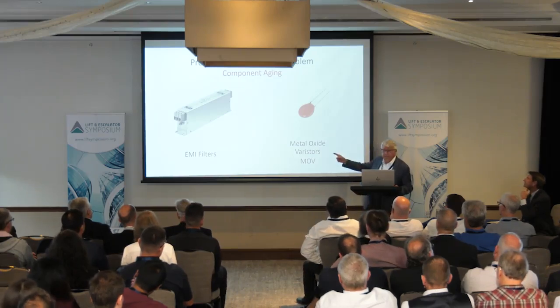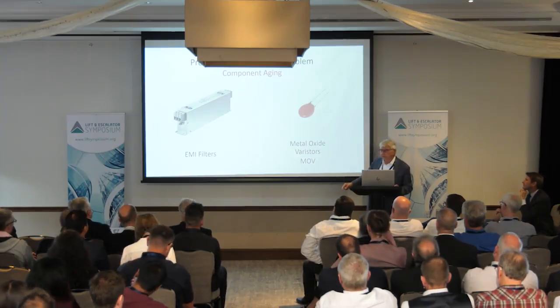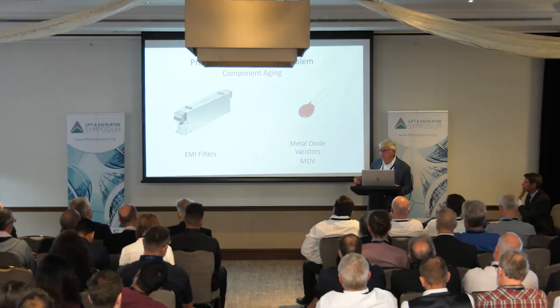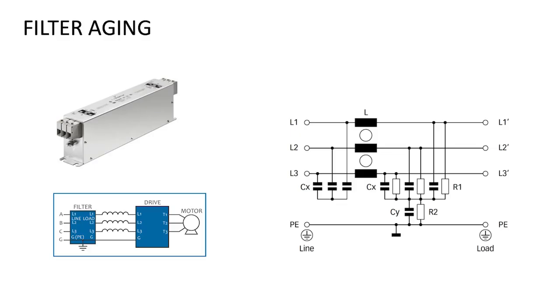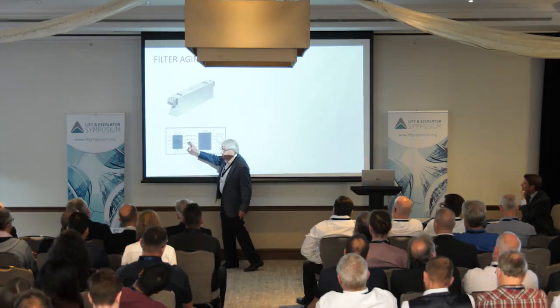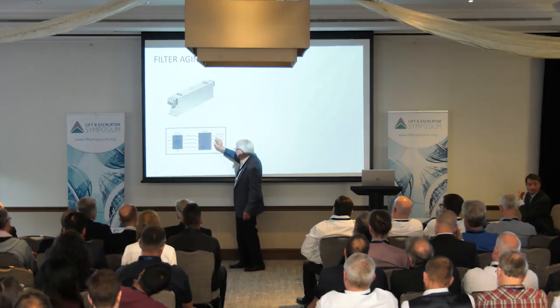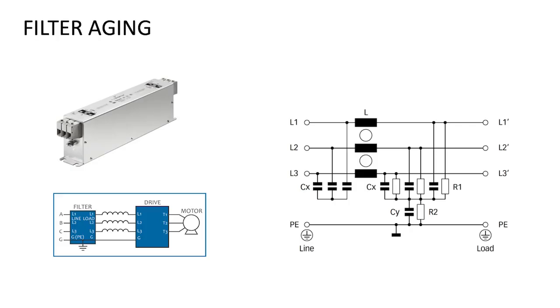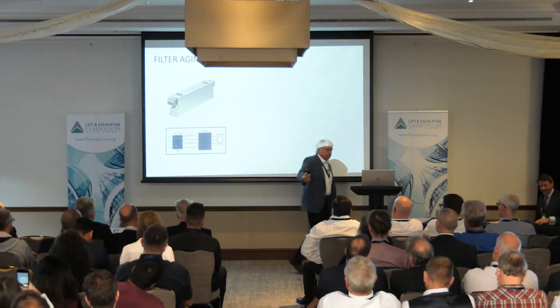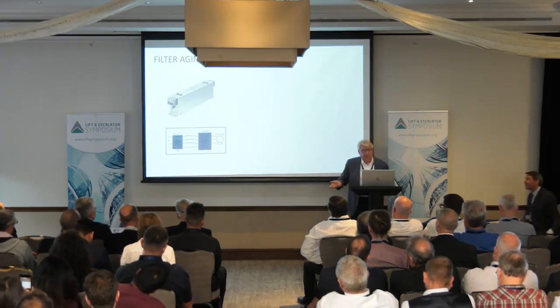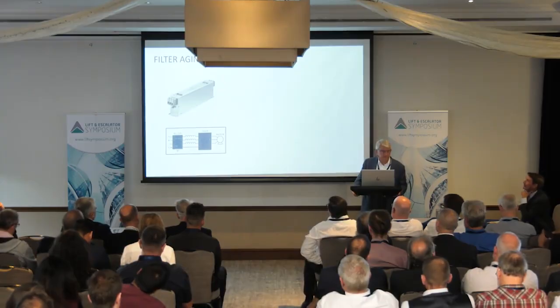You see these on the line side of variable frequency drives in Europe. Not required in the U.S. or Canada, but it's a good practice. What happens with these filters is, you have the incoming power, you have the filter, sometimes you put an inductor in here, usually not, and here's the drive and the motor. These keep the noise from the drive from going out, but they also keep any noise that's coming in. They'll eat the noise coming and going, so they're very effective.